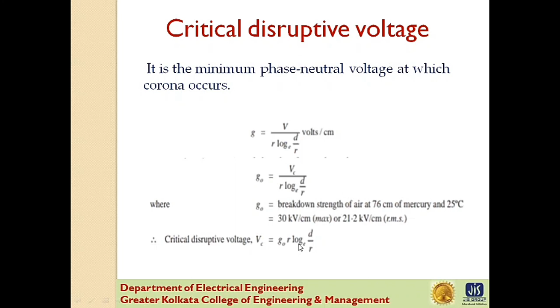So what is the new critical disruptive voltage? Vc equals G0 delta r log e d by r, so we multiply this expression by delta. Again we have to consider another factor: correction must be made for the surface condition of the conductor. This is accounted for by multiplying the above expression by m0. So the new critical disruptive voltage is m0 G0 delta r log e d by r kV per phase. This is important: the value of critical voltage is expressed in phase voltage.